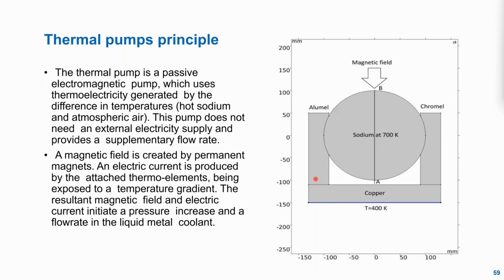Another point, we have the thermal pumps on the secondary loops. They are passive electromagnetic pumps. We use the thermoelectricity generated by the difference of temperature between the hot sodium and the atmospheric air. You see here on the view, we have the chromel and alumel wires. So there is a difference of temperature, and an electrical circuit will exist here.